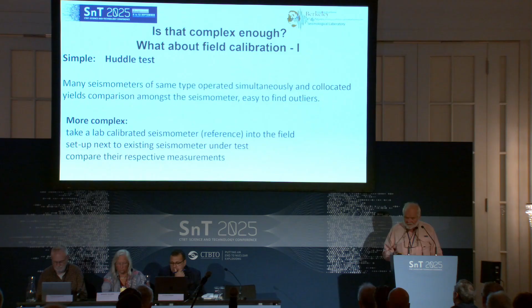The field calibration sounds straightforward, but there are lots of elements that one has to take into account. For instance, the reference seismometer. There's one saying in seismometry: the performance of a seismometer is not determined by the age of the seismometer, when it was built, but by how often it has been packed, closed, thrown on a transport truck, driven to a station and unpacked and so on. These are very delicate instruments, and every time you can have something happen to the seismometer. Mechanical vibrations and different environmental conditions determine its performance.